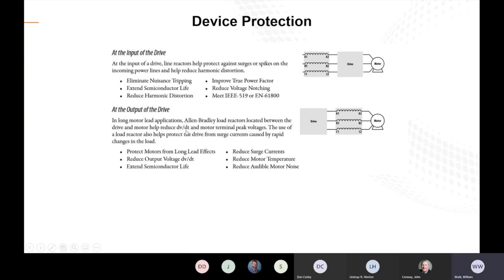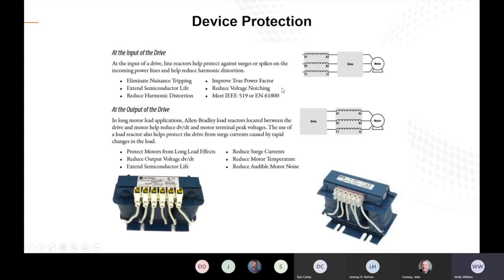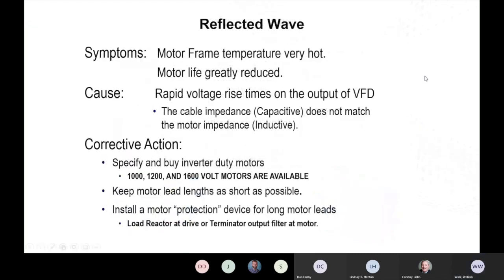You also might want to consider installing reactors on the output of your VFD as well, especially if you want to comply with IEEE 519, and if you have any issues with noise or harmonics. Here's just a couple of the line reactors that you'll see. This just goes into more detail about reflected wave and harmonics that you might experience, just depending on your lead lengths from the VFD to your motor. You can have vastly shortened motor life.